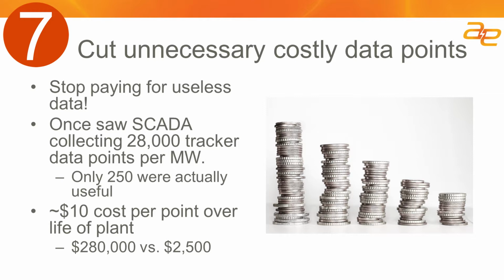So filtering out what data is valuable, what you can turn into actionable information for O&M to keep the system efficient and running, that's important. Back in my automation days, we always estimated that an analog point costs about $10 to implement as a life cycle cost, including the software to support it, integration into the software and HMI, and the historian. When you add that up, it costs about $10 to have an analog value in SCADA, and with 28,000 points it's just prohibitively expensive to collect everything. Quite frankly, most of it isn't necessary to determine whether the system's working well.